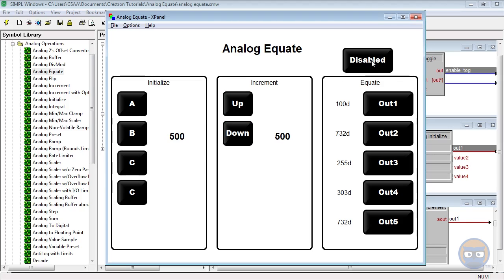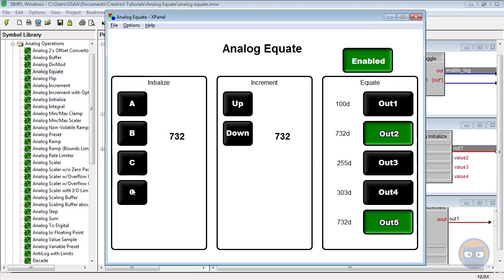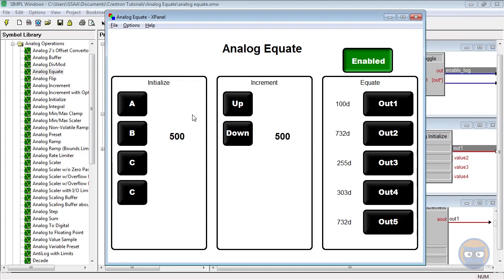But once the equate is enabled, that's when the magic starts to happen. Notice that when the analog value exactly equals one of the parameters inside of the analog equate, the corresponding digital output goes high.